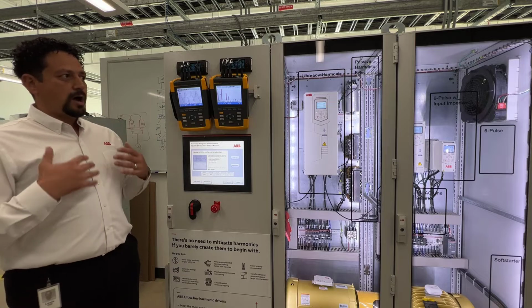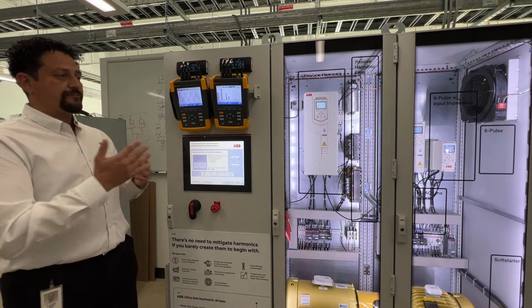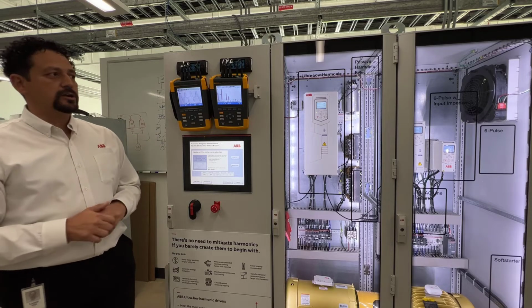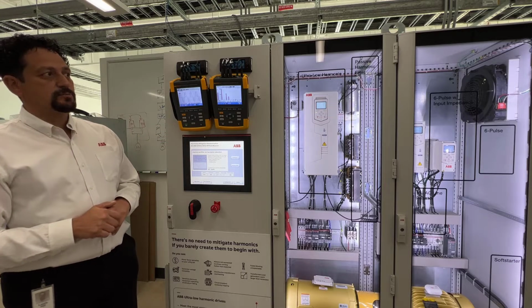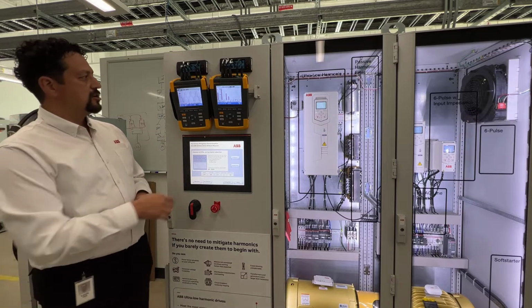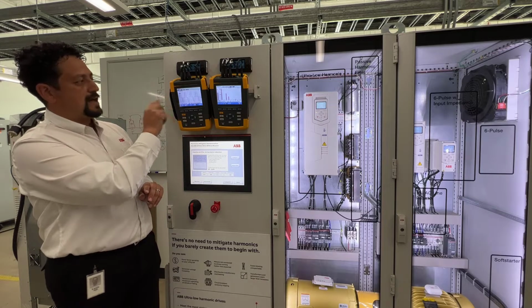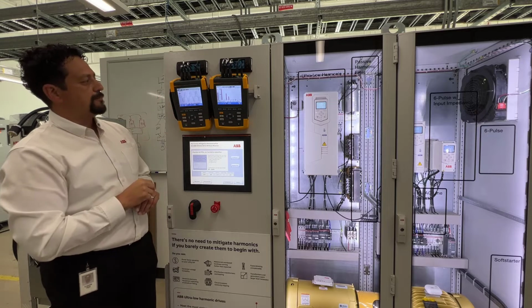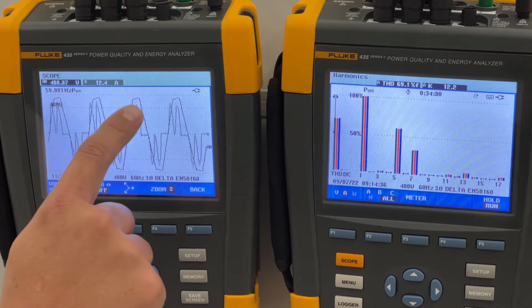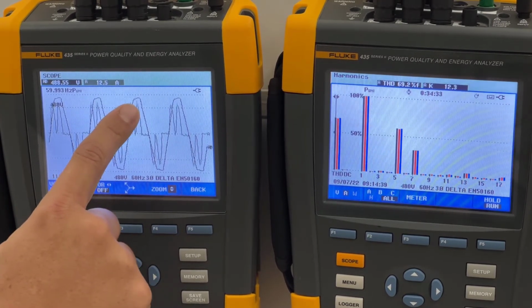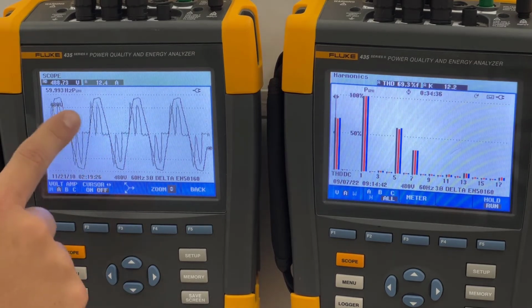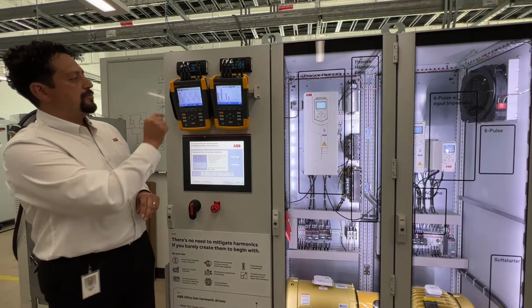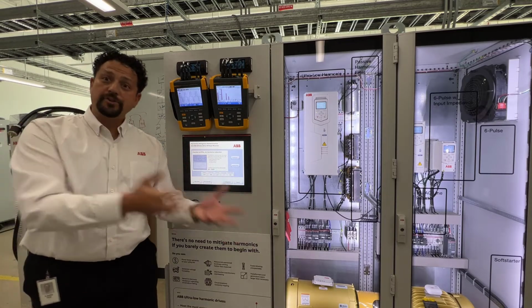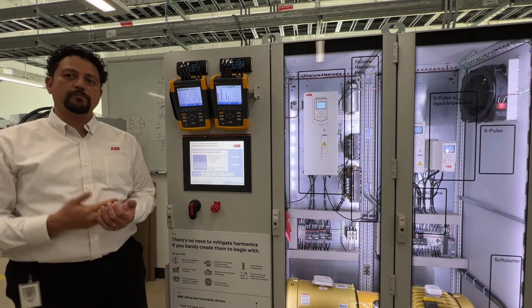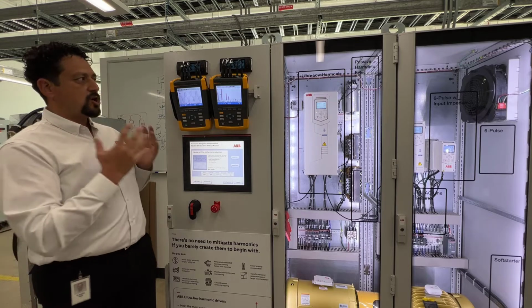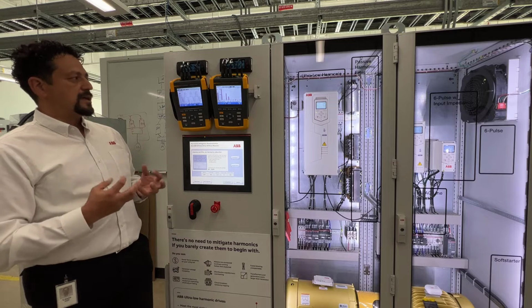When we look at harmonic performance of drives, we've got different levels that meet different requirements. The very first one we're going to talk about is the 6 pulse without any input impedance. Here we have two waveforms, the voltage waveform and the current waveform. On the voltage waveform, you can see a little clipping on the top. That's voltage clipping that happens as voltage distortion, and that's bad for your electrical network. You've also got these deep bunny ears, as we call them. That's your current distortion. That's the horse gulping the water. The deep bunny ears tell us we're sucking a lot of current down at one time, causing our electrical grid to take on and create all these harmonics.